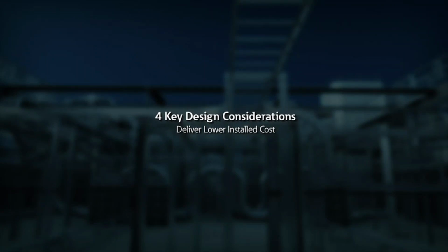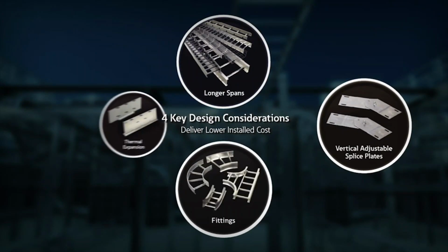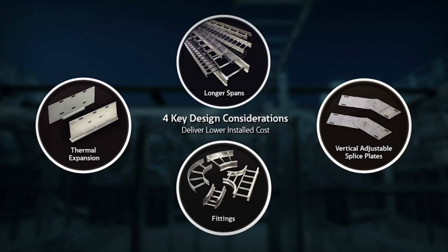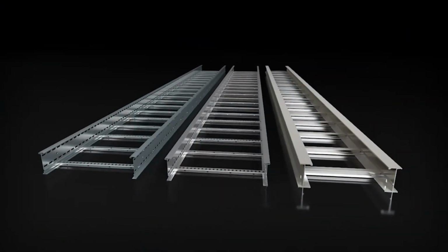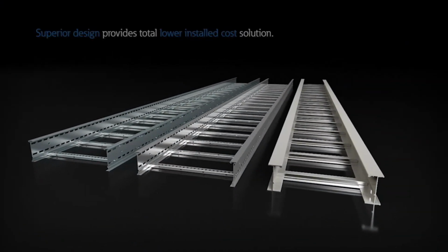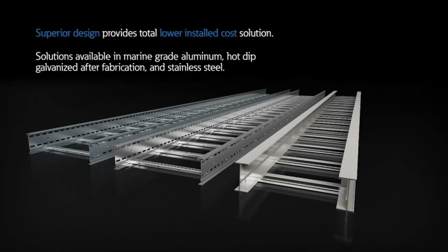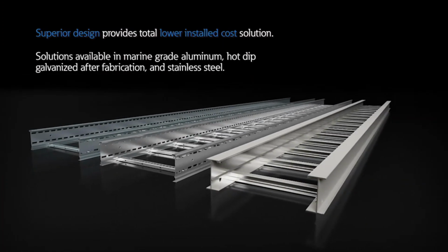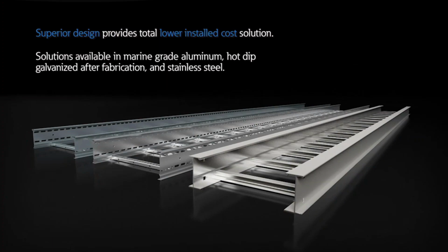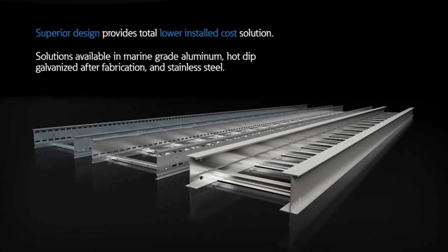This is accomplished by incorporating a number of features, including I-beam side rails for increased strength, splice plates that enhance structural integrity and allow for proper thermal expansion, as well as fitting design and use of tangents to maximize strength at fitting locations. All of these features result in a superior cable ladder system that allows customers to minimize their total installed cost by significantly reducing the number of structural steel supports.